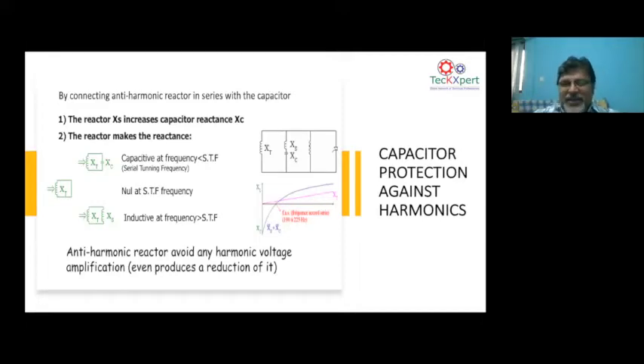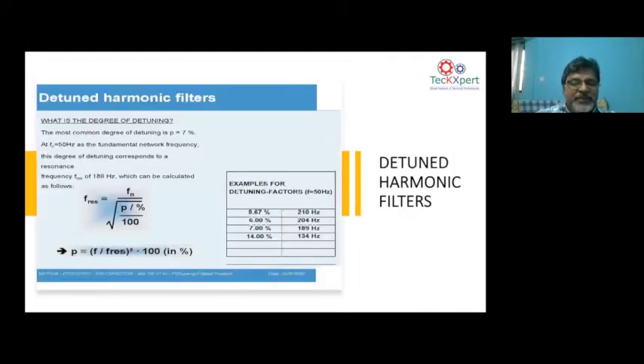Here again, putting a detuned reactor is not ultimately a solution to deal with harmonics. This is only to protect your capacitor bank. The harmonics will still be there. How to treat the harmonics is a separate subject, but now we are only ensuring that your capacitor banks are protected from harmonics, but the harmonics are still there. Go to the next slide.